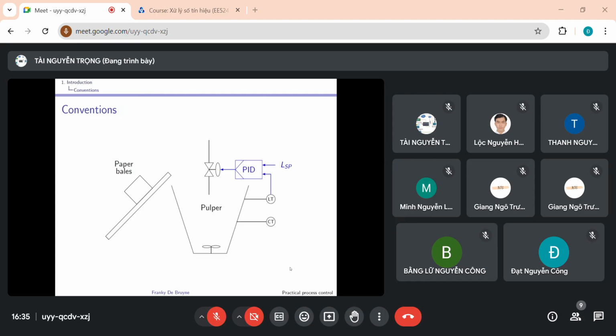You will see that the representations of a PID controller in a P&ID and in this course are often simplified. So this is the PID controller as you know it, represented as you know it. So here it's acting on a pulper. The PV is a level measurement, as you can see, because we have a measurement coming from a level transmitter. Inside, the control error is constructed, so the level set point minus the level measurement, right?